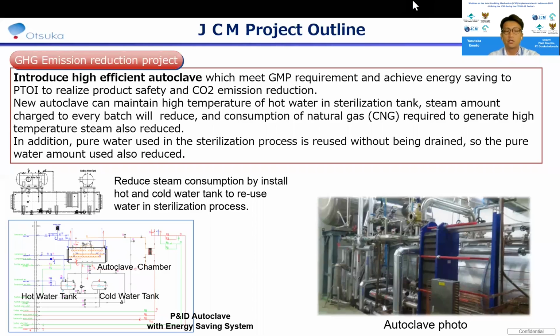Next is the JCM project outline. As a GHG emission reduction project, we introduce a high efficiency autoclave which meets GMP requirements and achieves energy saving at Ptoi, to realize product safety and CO2 emission reduction. The new autoclave can maintain the high temperature of hot water in the sterilization tank, and we can reduce the steam amount and consumption of natural gas and high temperature steam. In addition, we can also reduce pure water usage.